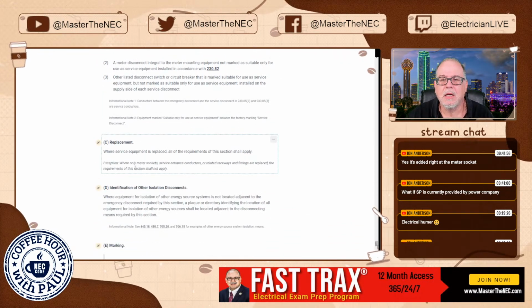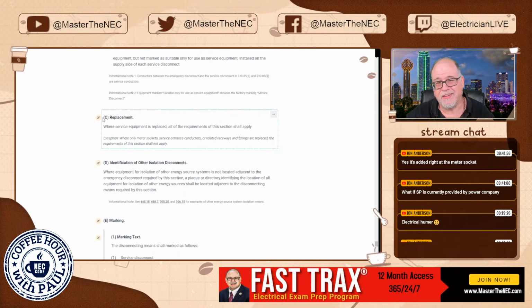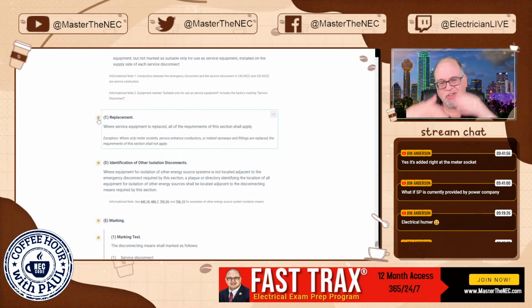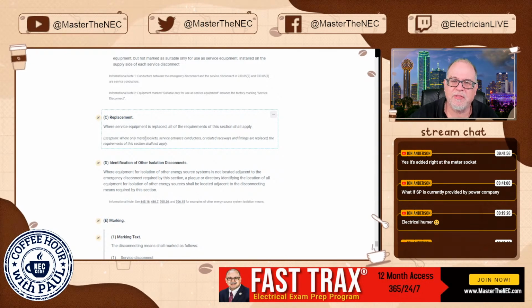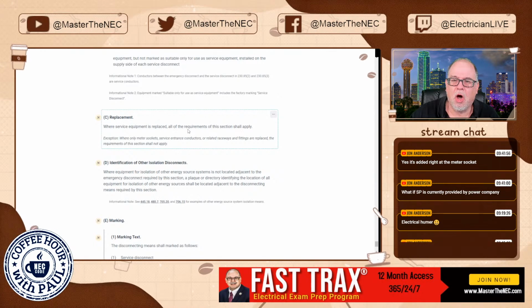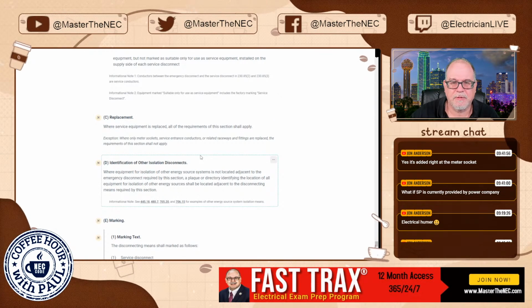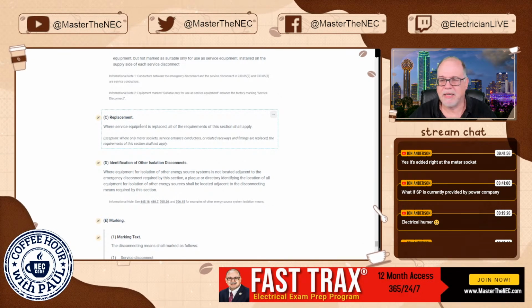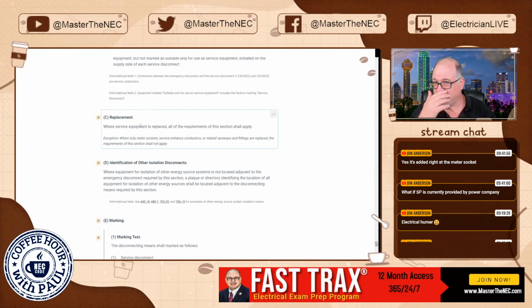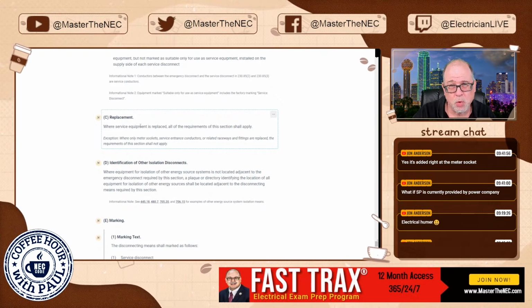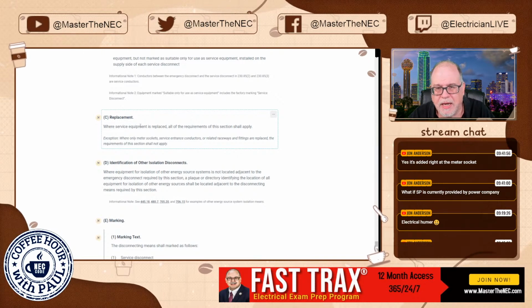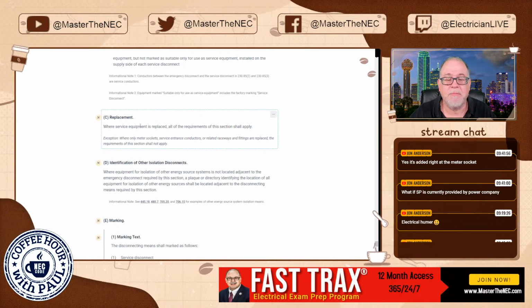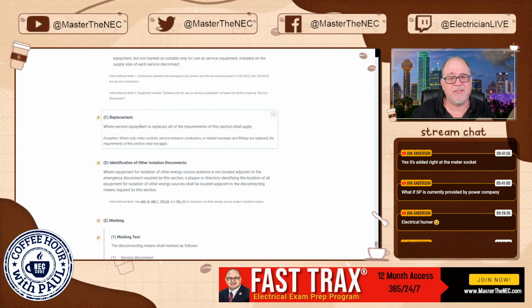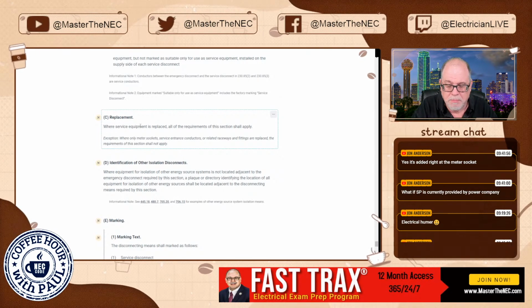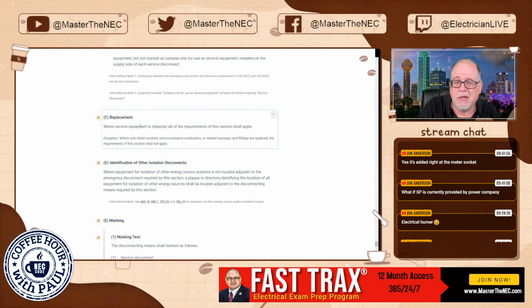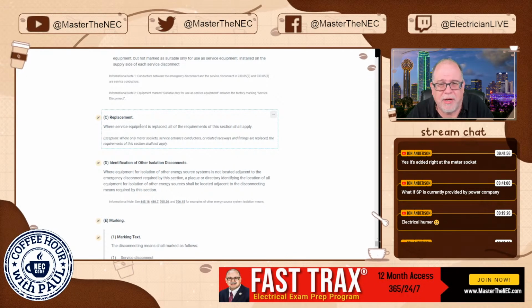All right. Replacement is this rule. This is, again, not new, but it's just a new structure. So where service equipment is replaced, all of the requirements of this section shall apply, right? Now, there's an exception. So if I'm doing a service change, now in many states, they have what's called like-for-like rules. If I take 100 amp and I replace it with another 100 amp, that is replacing it unless the exception is going to apply here. So maybe I'm going from fuses, 100 amp, to maybe I'm going to circuit breaker, 100 amp.